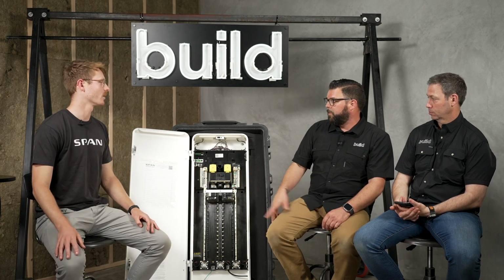Same SKU. And while we're on configurability and SKUs, we support a main breaker between 100 and 200 amps, with 175, 150, and 125 as well. This is field swappable, and it's a Square D main breaker, QOM2, so I could go to my Square D supplier right down the street and pick one up.